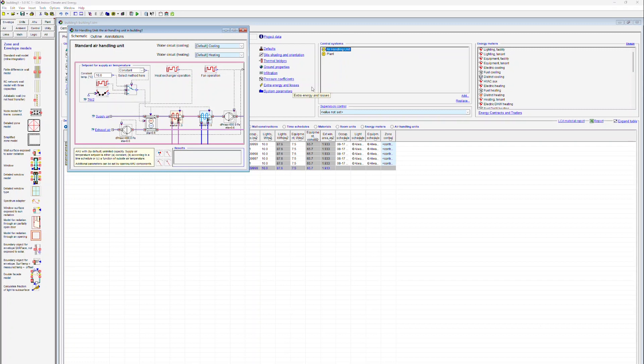In the standard air handling unit there are three different ways how the user can specify the temperature of the supply air. The first option is the definition of a set point for the supply temperature. In this particular case we're setting this to 16 degrees.